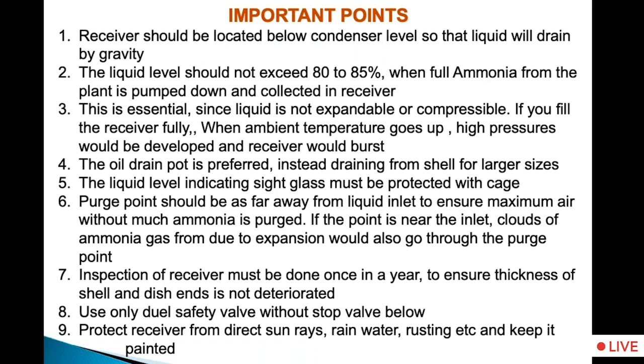In one of the plants, I had to literally lower the receiver, and there was no space in the plant room, so I had to hang it from the ceiling level by fixing a bracket to get a distance between the condenser outlet and the receiver inlet. This should be, in my opinion, at least 1.5 to 2 feet between the condenser outlet and the receiver inlet. The oil drain pot I have already talked to you about. There is a liquid level gauge glass. The purge point should be as far away as possible.